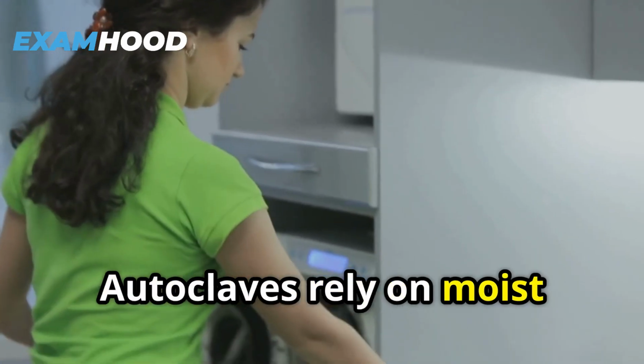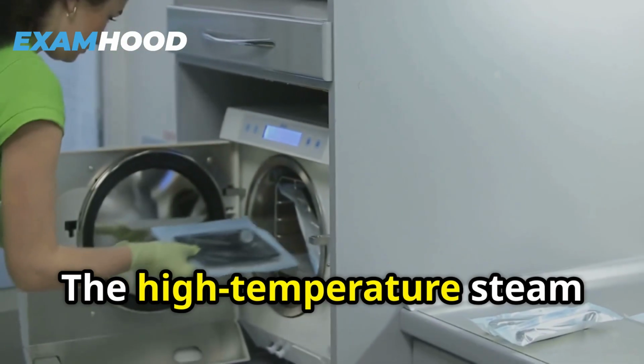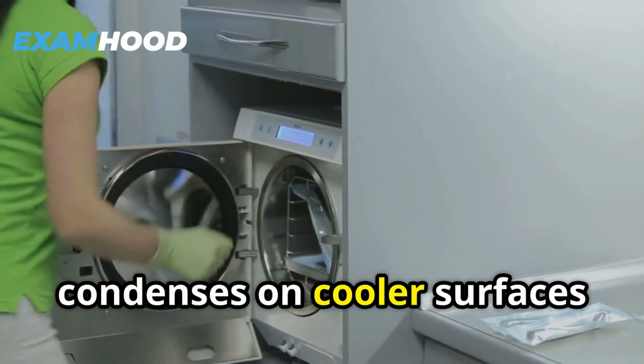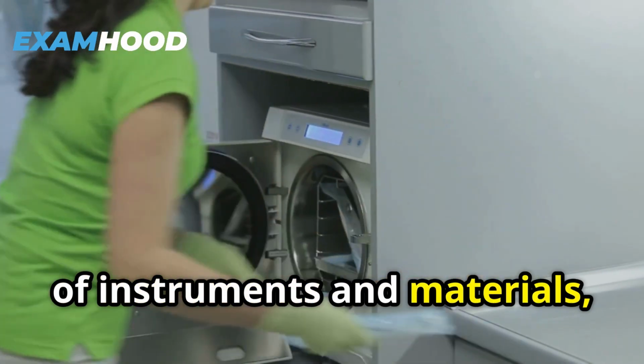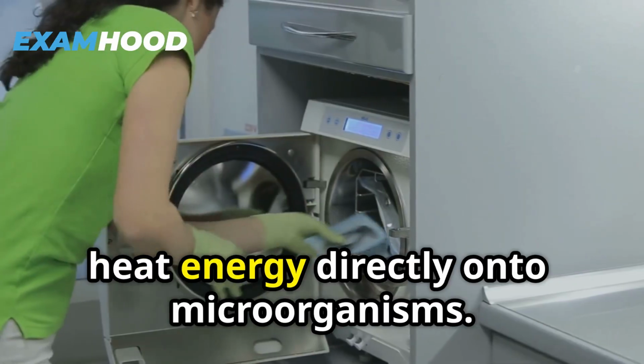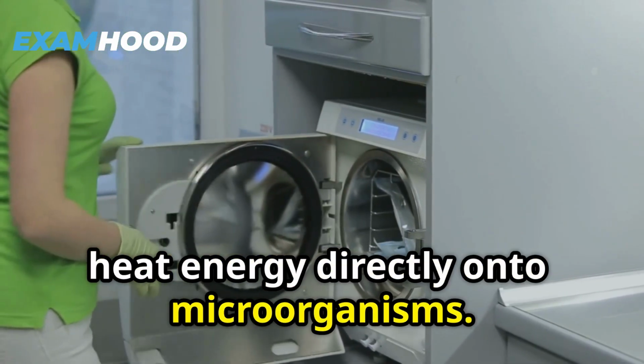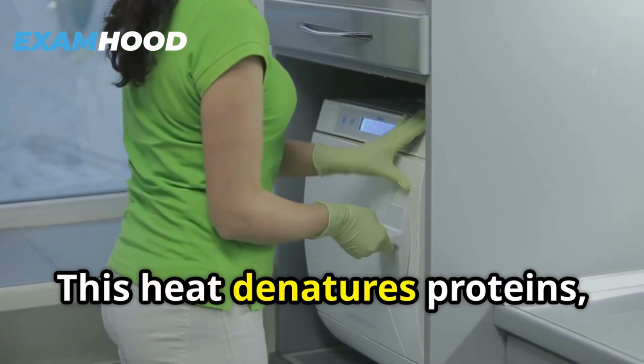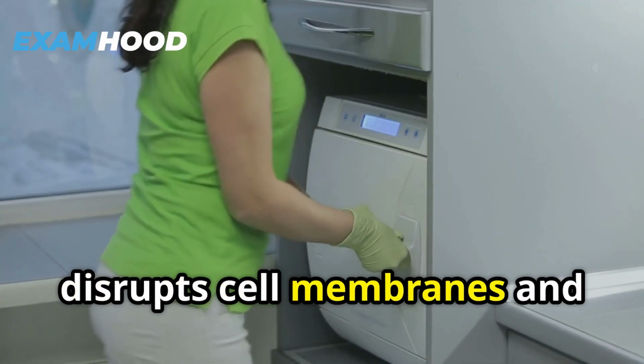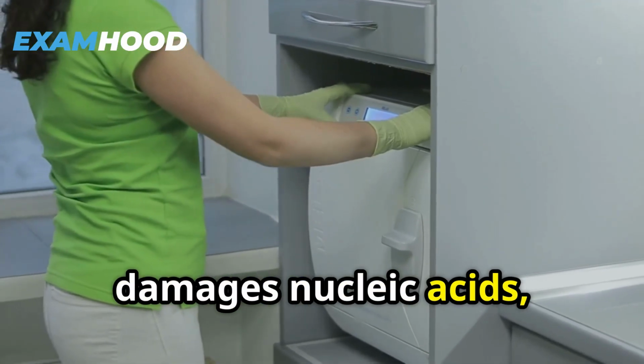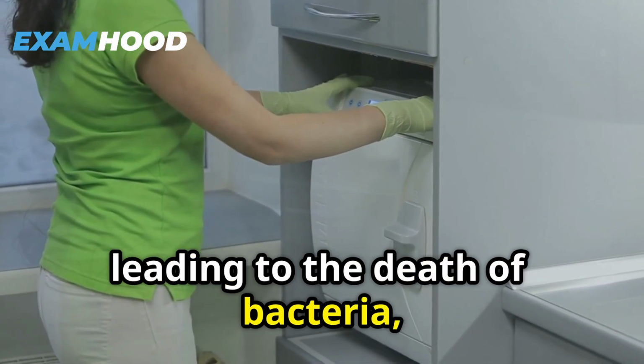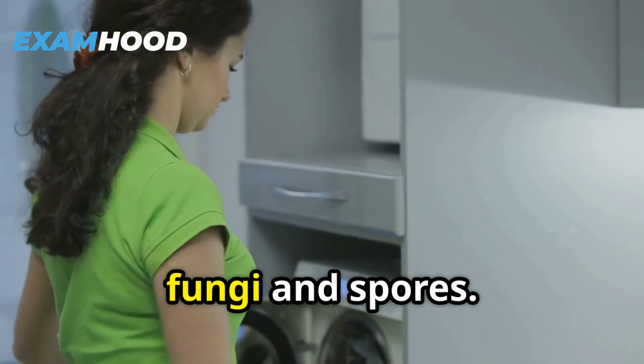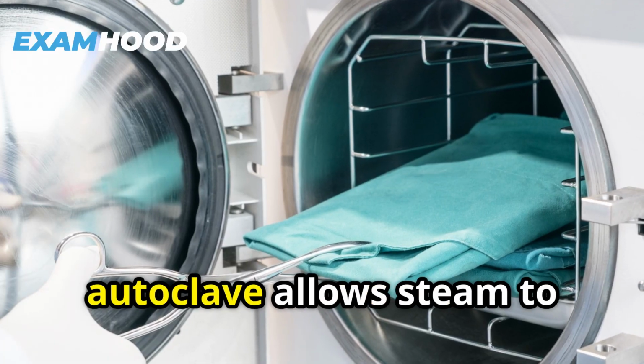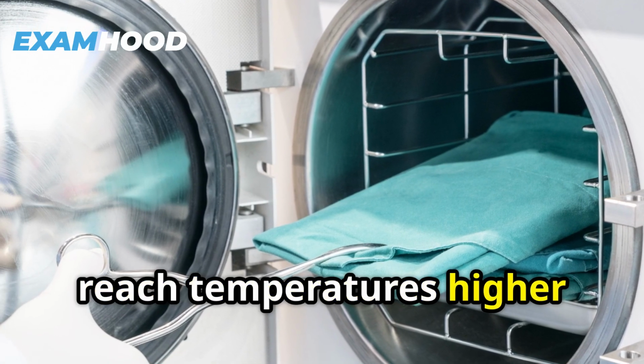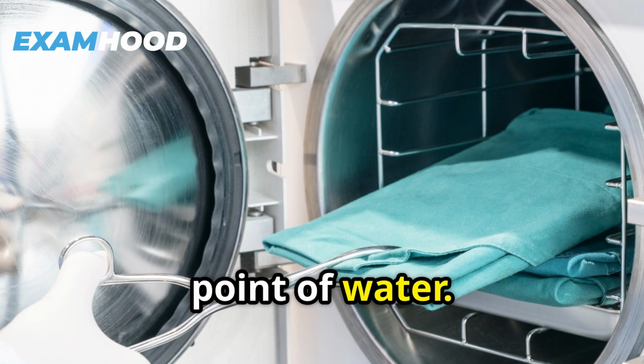Autoclaves rely on moist heat sterilization. The high-temperature steam condenses on cooler surfaces of instruments and materials, releasing a large amount of heat energy directly onto microorganisms. This heat denatures proteins, disrupts cell membranes, and damages nucleic acids, leading to the death of bacteria, viruses, fungi, and spores. Pressure inside the autoclave allows steam to reach temperatures higher than the normal boiling point of water.